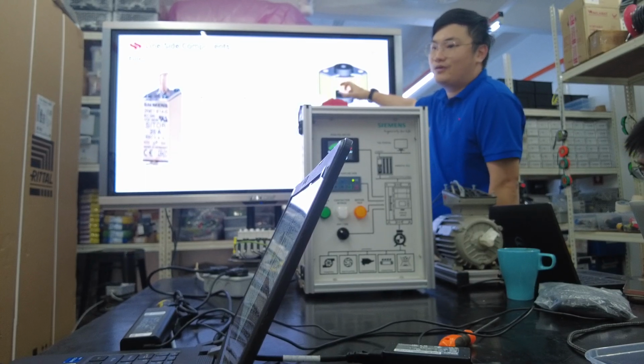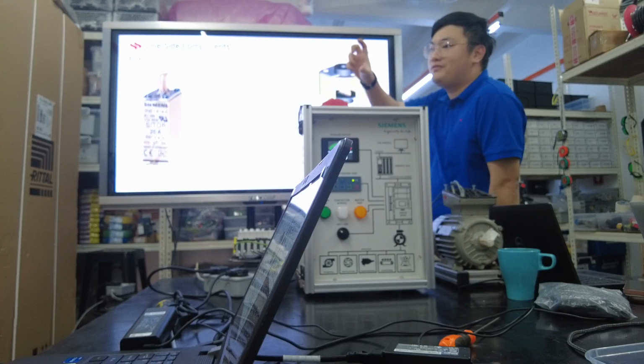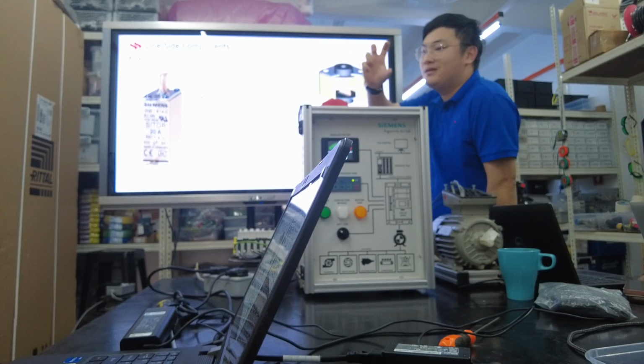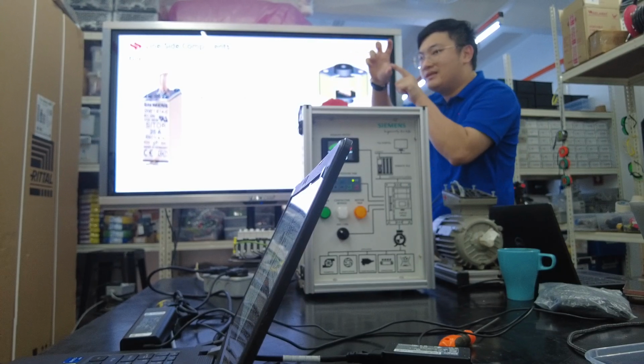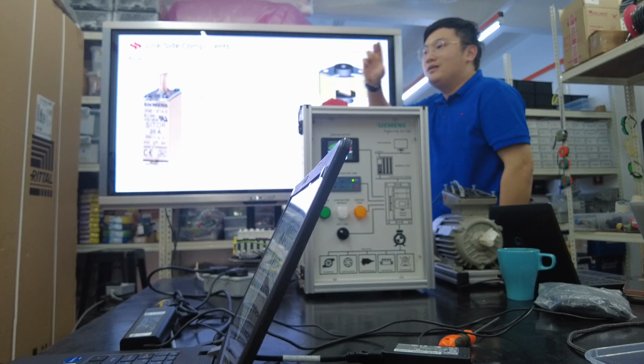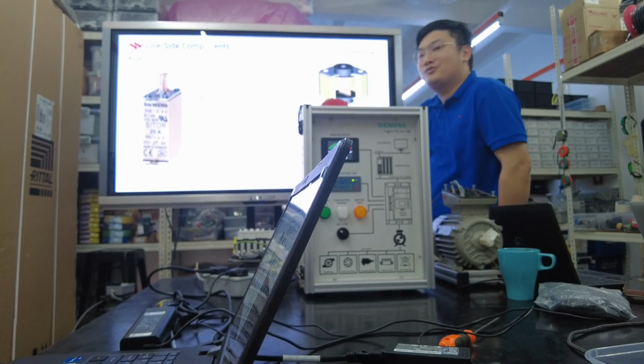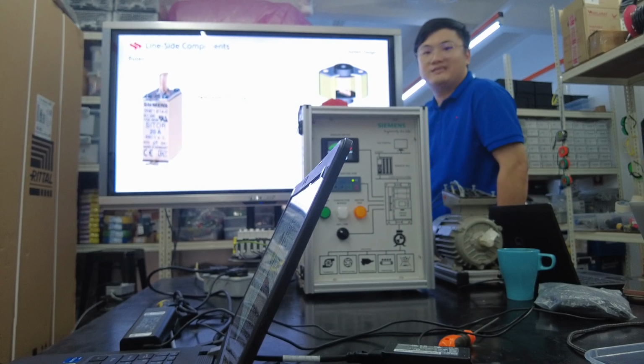So commonly we use this. If you use a normal fuse, usually inside it's hollow - just a copper cable straight to the front. So this has a problem - if the panel is hot, it breaks faster; if it's cold, it breaks slower. But my inverter's duty operation is from negative 40 up to positive 70.